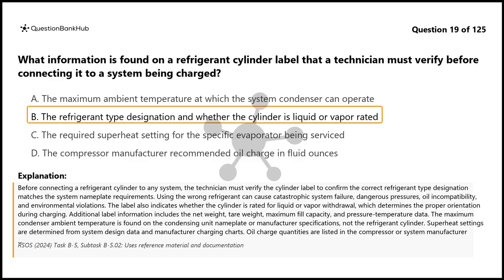The maximum condenser ambient temperature is found on the condensing unit nameplate or manufacturer specifications, not the refrigerant cylinder. Superheat settings are determined from system design data and manufacturer charging charts. Oil charge quantities are listed in the compressor or system manufacturer documentation.